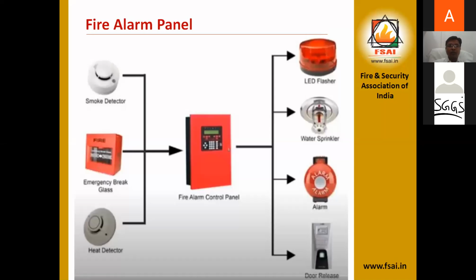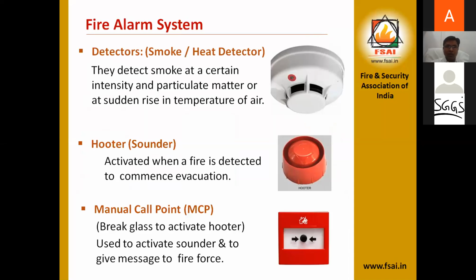The first one is the detectors. There are two kinds of detectors, smoke detector and heat detector. They detect smoke at a certain intensity and particulate matter, or a sudden rise in the temperature of the air. So when any fire occurs, the temperature of that area increases and this detector notes the rise in temperature so that it starts giving a signal.